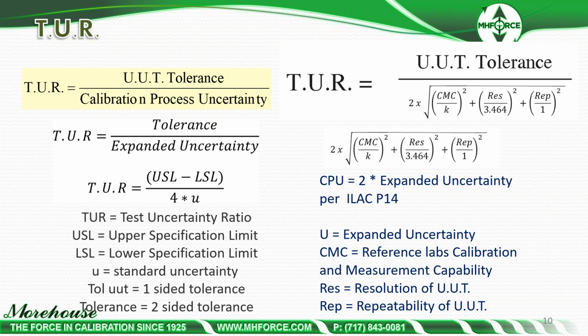ILAC P14 makes reference to the resolution. I know the test uncertainty ratio people hate this, but it is something that is in ILAC P14, as well as ANSI Z540 Handbook 3 talks about a lot in reference to the denominator. These are really what it says are the minimum things to consider in a denominator, which are your CMC uncertainty parameter, divided by whatever coverage factor you used. Resolution, here I'm taking the square root of 12 because I'm assuming it's digital.